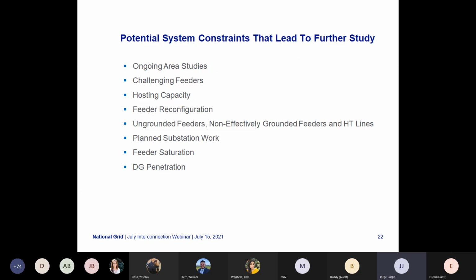Some of the potential system constraints that lead to further study are ongoing area studies, challenging feeders, and hosting capacity. If a feeder just has too much DG oversaturation, we need to send it to further study to see how we can interconnect the system. Also, any substation or feeder reconfigurations, and anything on a non-effectively grounded or ungrounded feeder. Next slide, please.